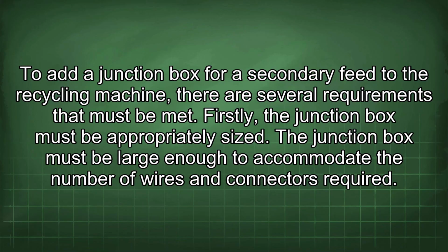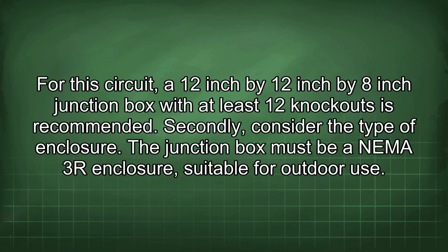To add a junction box for a secondary feed to the recycling machine, there are several requirements that must be met. Firstly, the junction box must be appropriately sized. The junction box must be large enough to accommodate the number of wires and connectors required. For this circuit, a 12-inch by 12-inch by 8-inch junction box with at least 12 knockouts is recommended.